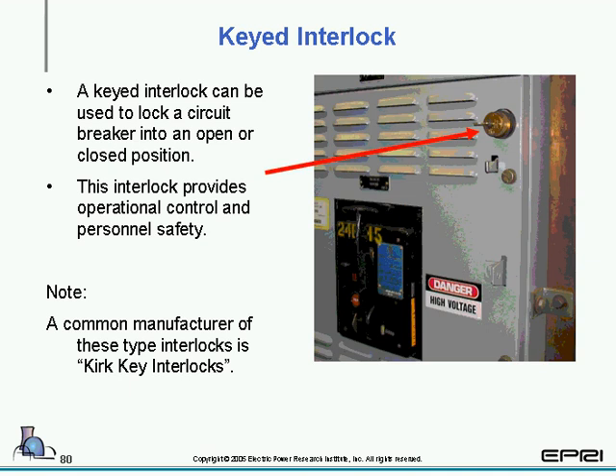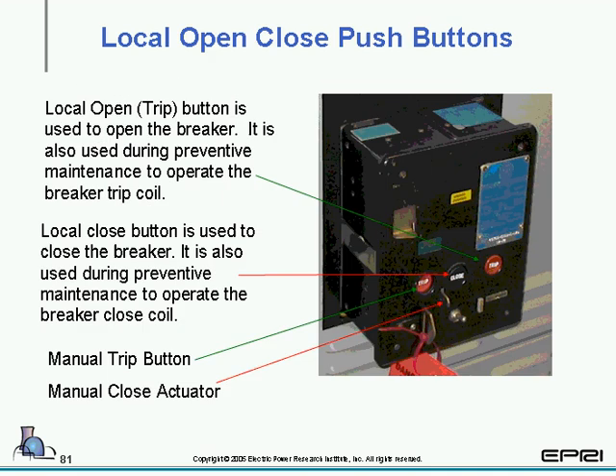Next one to take a look at is keyed interlocks. Now, keyed interlocks can be used to lock the circuit breaker into an open or closed position. This interlock provides operational controls for personnel safety. And a key note, one of the common manufacturers is Kirk Key. So it's often referred to not as a keyed interlock, but as a Kirk Key.